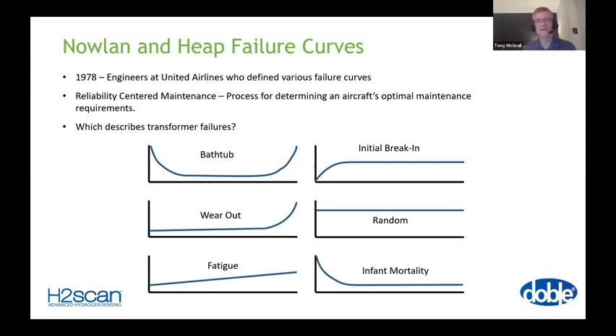Now, admittedly, they were working in the airline industry, different components to what we're used to. But in addition, we've seen this analysis applied in the medical industry, in the electric supply industry, in mining, in oil rigs, and it's generally the same frequency: the bathtub curve only applies to about 4% of asset types. And if you reference back to the CIGRE technical brochure Leon mentioned earlier, within that they've got failures not just from 7,500 transformers from the US, but from more than a dozen different countries, thousands and thousands of transformers. And when you looked in total, there was no indication of a bathtub type curve.